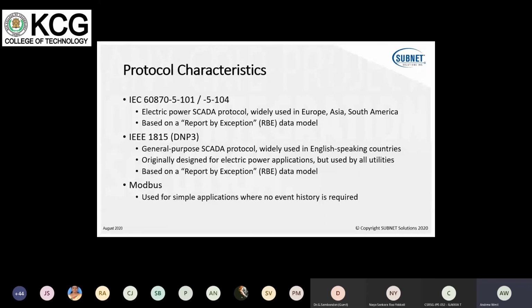You will sometimes see Modbus for simple applications or talking to PLCs. Modbus does not have a report by exception kind of model, has no event history kind of model, but for simple applications, it's easy to use. For more complex applications, it quickly becomes expensive to engineer because of the way that the data is typically used by most devices. But I don't want to spend time talking about it.